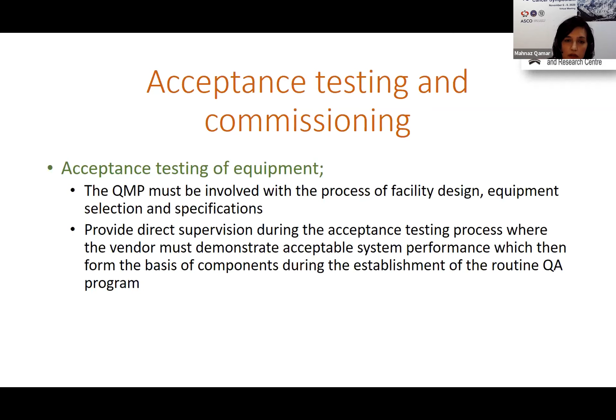In the acceptance, testing, and commissioning process, they provide direct supervision during the acceptance, when they're accepting the machine from the vendor. They work closely with the installer and their engineers to perform the acceptance testing process, where the vendor demonstrates acceptable system performance, some of which then forms the basis of components during the establishment of the routine QA and the commissioning process. If we accept the machine at the very edge of tolerances, then it would be hard to maintain that. And once you accept it, it's not easy to go back and ask them to tighten the system or change the tolerances.